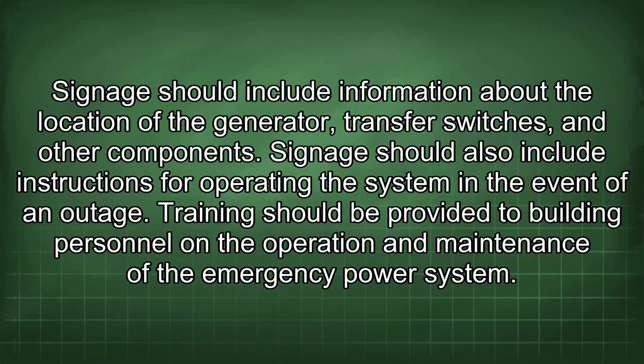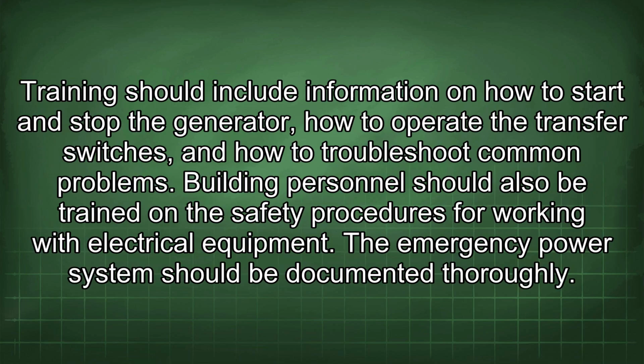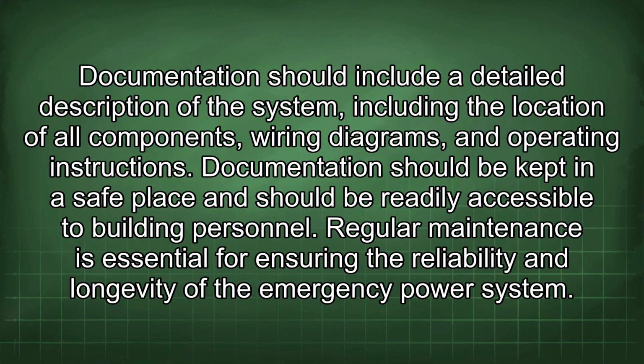Training should be provided to building personnel on the operation and maintenance of the emergency power system. Training should include information on how to start and stop the generator, how to operate the transfer switches, and how to troubleshoot common problems. Building personnel should also be trained on the safety procedures for working with electrical equipment. The emergency power system should be documented thoroughly. Documentation should include a detailed description of the system, including the location of all components, wiring diagrams, and operating instructions. Documentation should be kept in a safe place and should be readily accessible to building personnel.